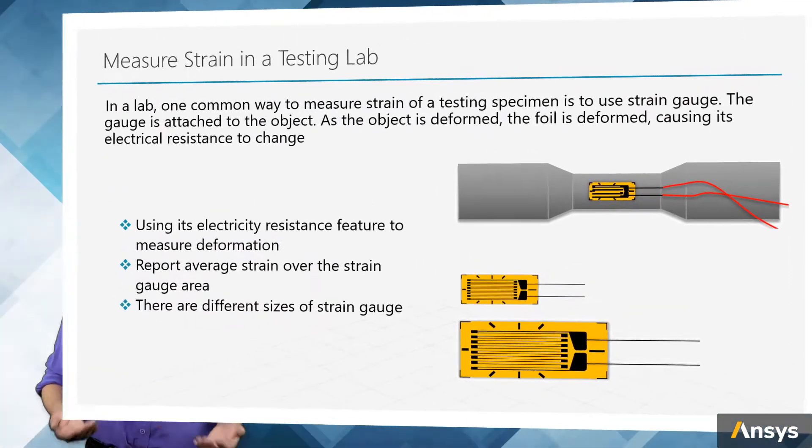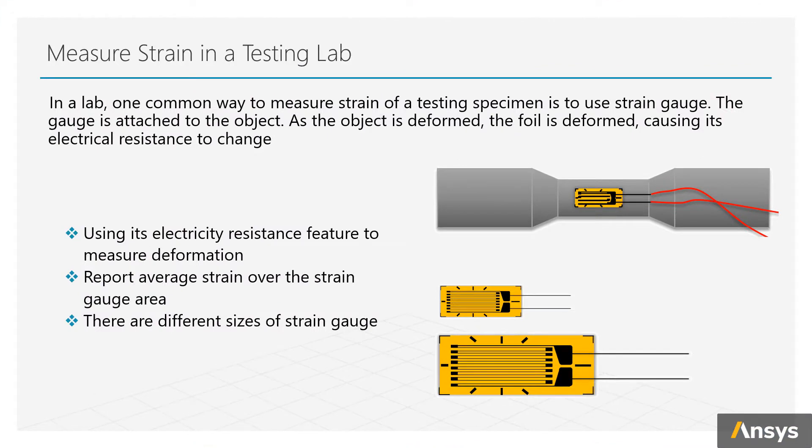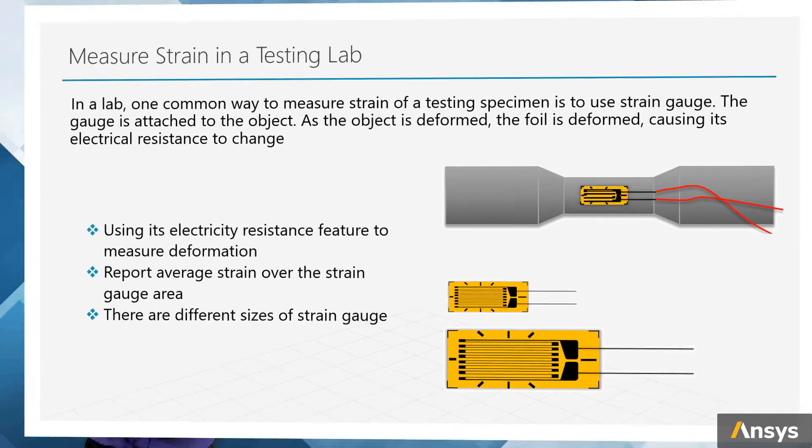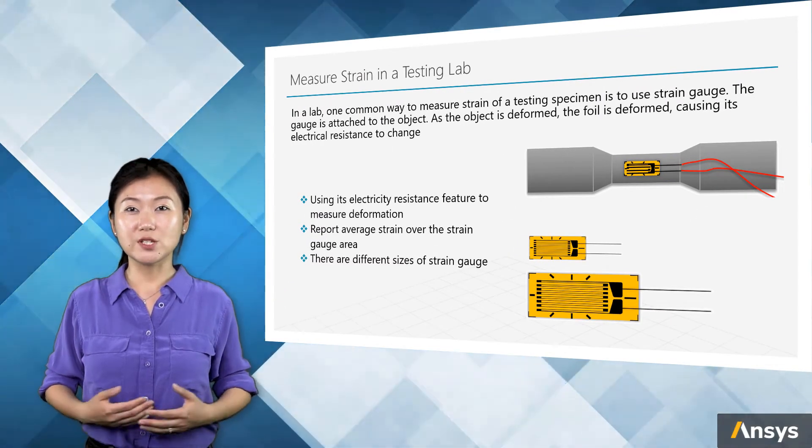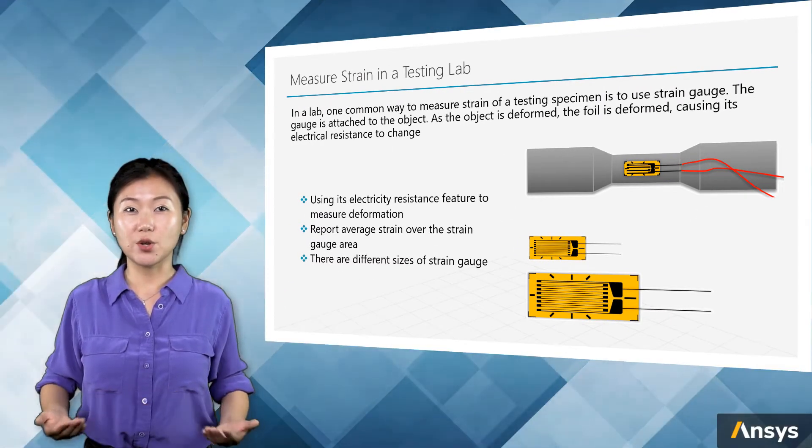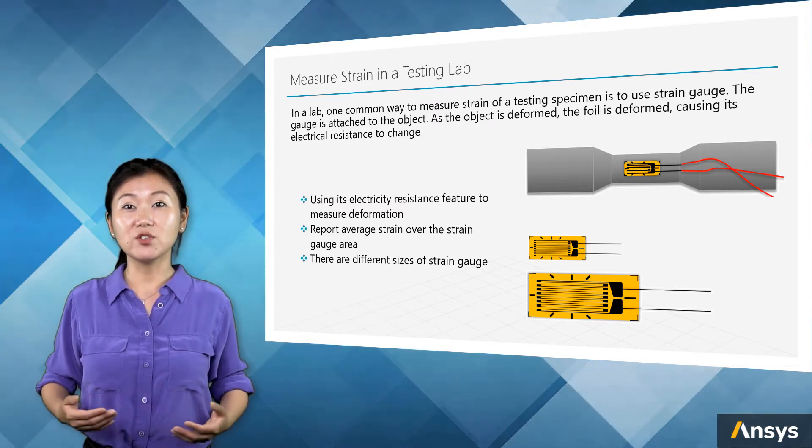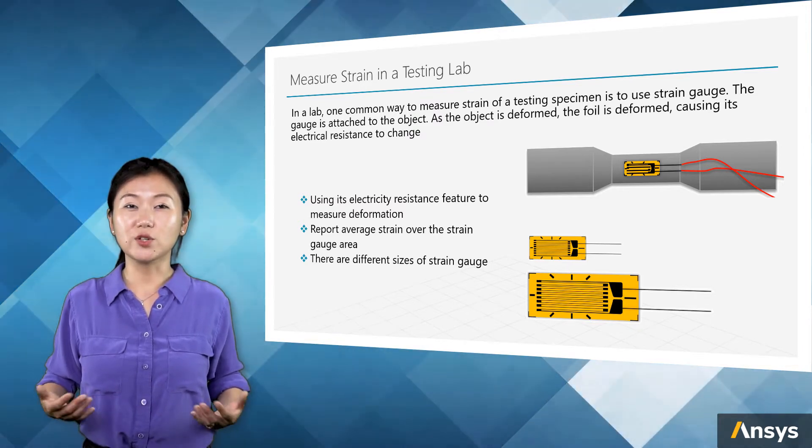So in a testing lab, one common way to measure strain of a specimen is to use strain gauge. The gauge is attached to the object. As the object is deformed, the foil of the strain gauge is deformed, causing its electrical resistance to change, so that strain is detected and reported. Note that the reported strain is an average value over the strain gauge area, and there are different sizes of strain gauge to use for different situations.